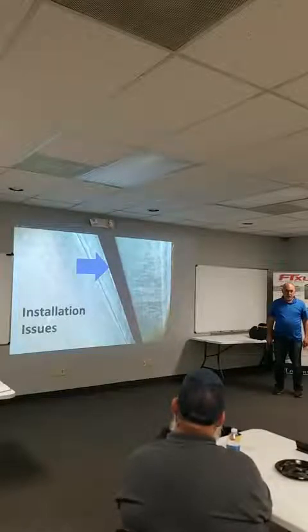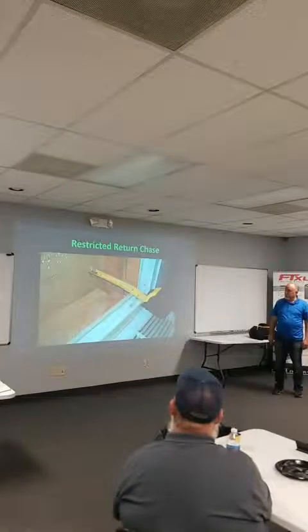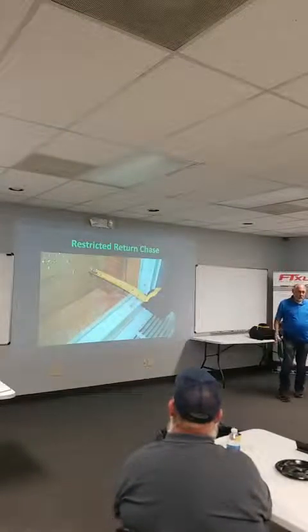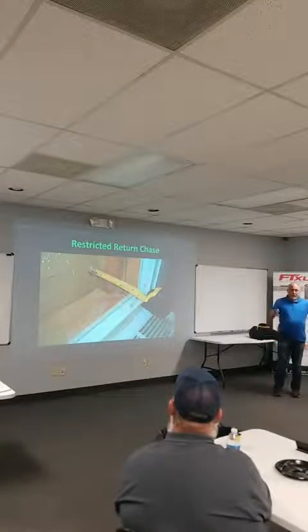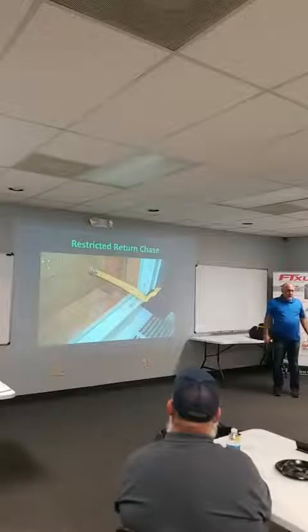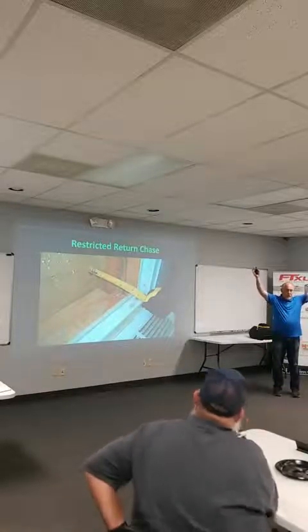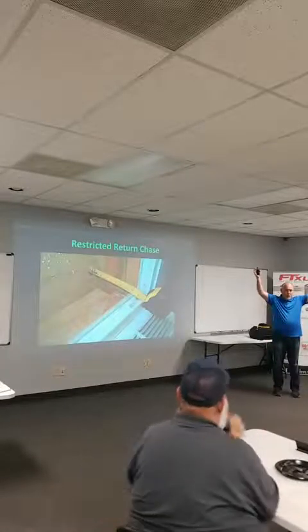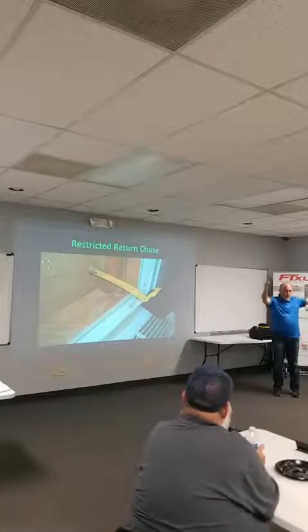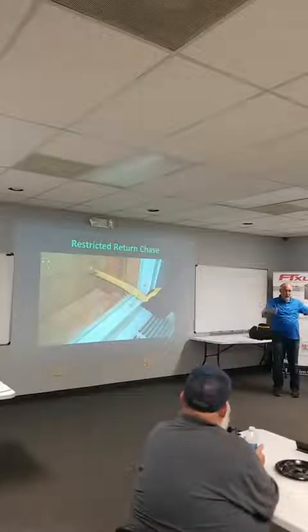Air's not going through that coil, air's gonna go around it. As soon as the coil gets wet, all this cooling's bypassing the coil, right? This is another one we're seeing a lot. You guys hear about the big drop? Guys are putting 20 by 25, 20 by 20 drops on residential equipment now to get the air velocity down, with bigger filters, right?